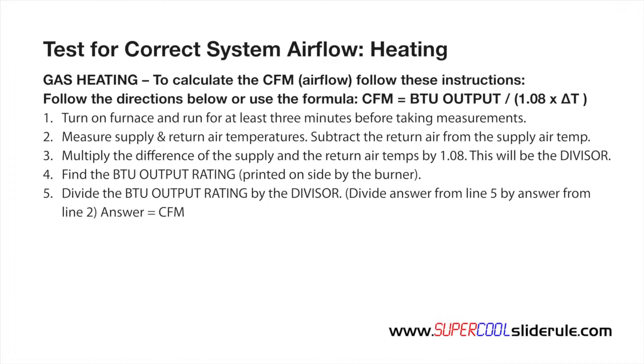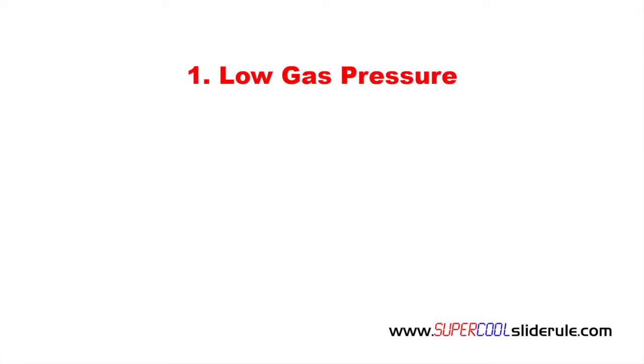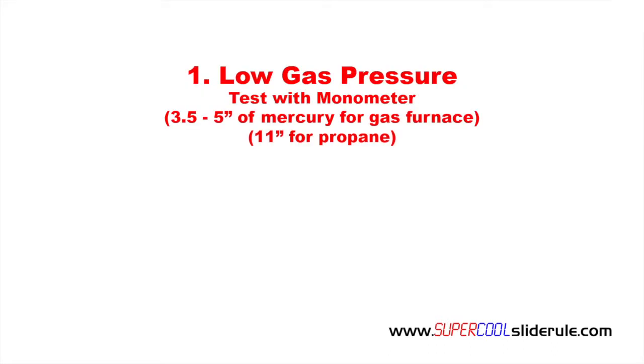If the delta T is too low, the primary causes are low gas pressure. Test the gas pressure with a manometer; ensure that it is between 3.5 to 5 inches of water column on natural gas and about 11 inches on propane.